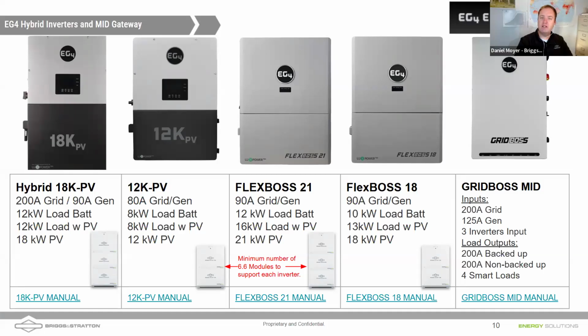Another consideration, though, is the ability for a battery to discharge itself. Its C rate, how fast we can discharge a battery while not damaging it. With a full stack, right, a 3 stack of 6.6 batteries, the continuous output is 14,000 watts. So you can see here on the left with that hybrid 18K PV, we need a full stack of 3 batteries to support the 12,000 watts from batteries to loads that hybrid inverter might be asking for. A 2 stack can supply 10,000 watts, 10,600 watts to be precise.